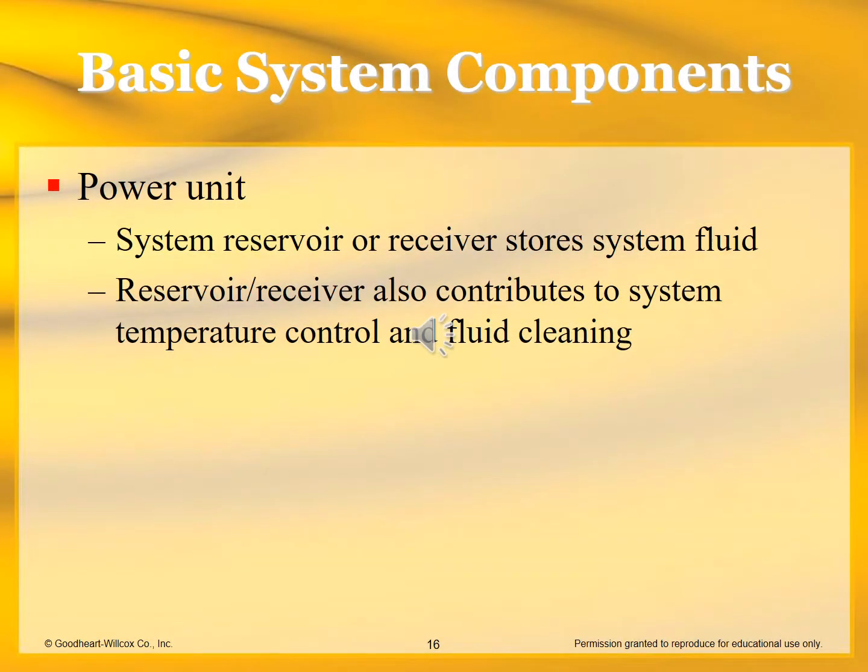Okay, you tack on a big tank to store the extra oil not being used in the system. You've got a reservoir, and you put that on your pump. Combine it with your pump, you've got a power unit. A couple of things the reservoir does: since it's just sitting there, it also cools the oil, and it also allows dirt to settle out of the oil. So it cleans and cools it at the same time.